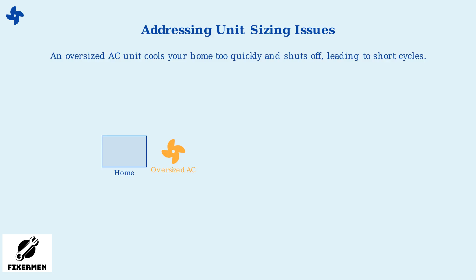An oversized AC unit cools your home too quickly and then shuts off, leading to short cycles. This rapid on-off cycling wastes energy and stresses the system. Proper sizing requires Manual J calculations, which determine your home's exact cooling load based on factors like size, insulation, and climate. This matches the unit's BTU capacity precisely.